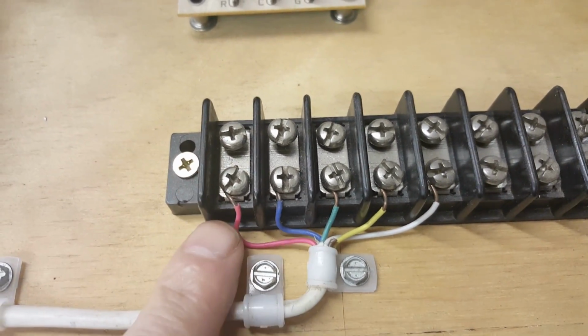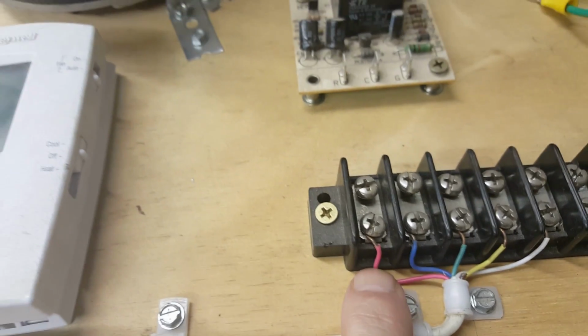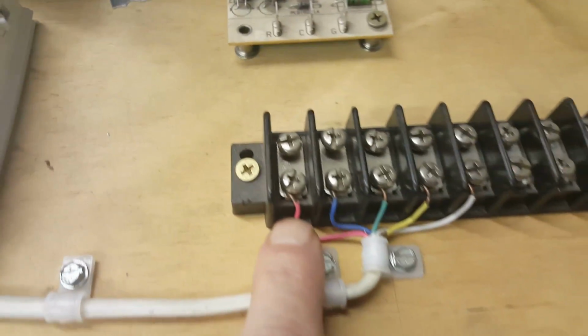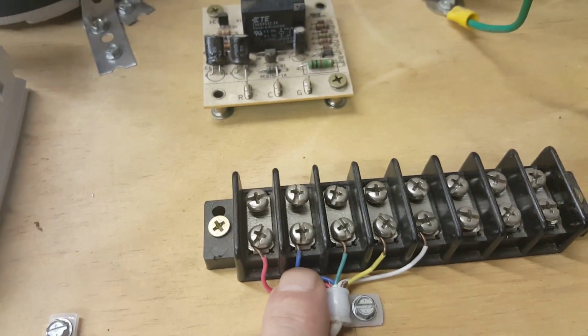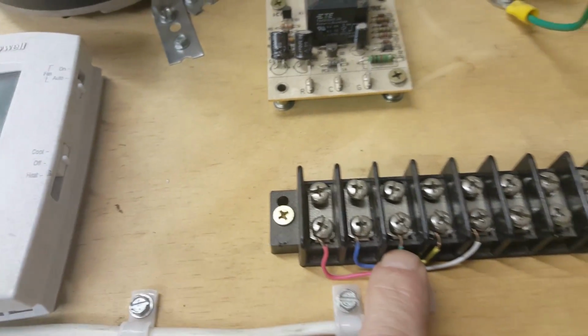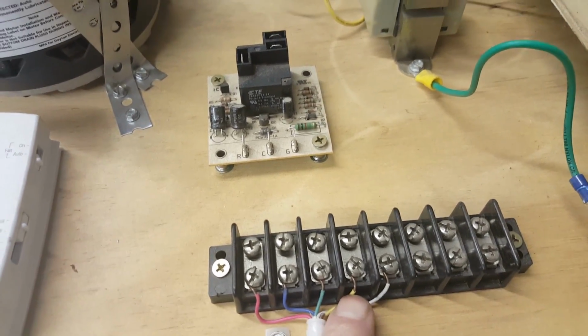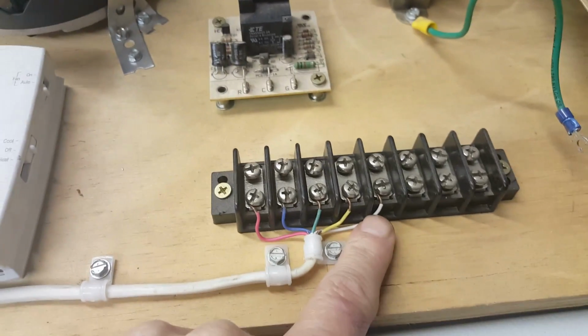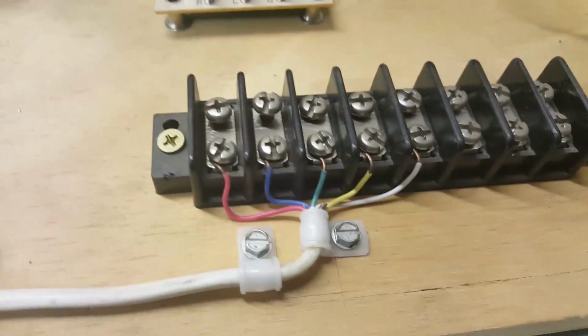But typically you have your 24 volt power and your 24 volt common here where your transformer is coming into the system. And then we're going to use R for the power wire if we're color coding, which we want to, but don't depend on it. We're going to use blue for the common wire going out to the thermostat, and G for the fan circuit. That's your green wire. We got yellow for our Y circuit, which is our cooling wire circuit, and we have white, which is our W circuit, which is our heating circuit going out to the thermostat. So there's 5 wires going out to the thermostat.